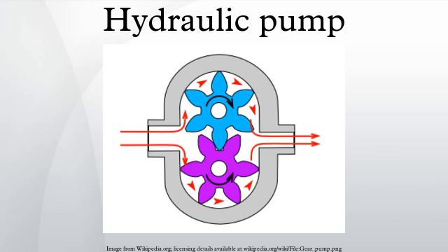Some gear pumps can be quite noisy compared to other types, but modern gear pumps are highly reliable and much quieter than older models. This is in part due to designs incorporating split gears, helical gear teeth and higher precision quality tooth profiles that mesh and unmesh more smoothly, reducing pressure ripple and related detrimental problems.